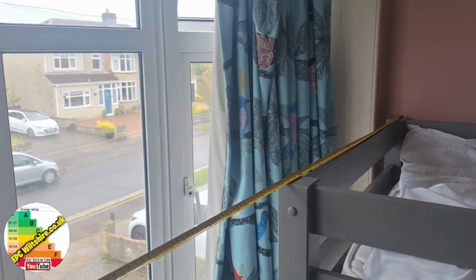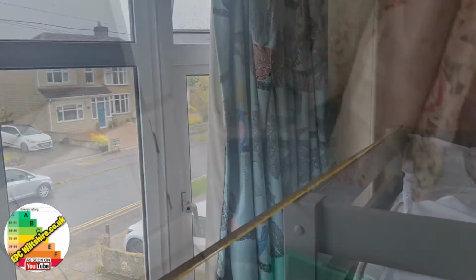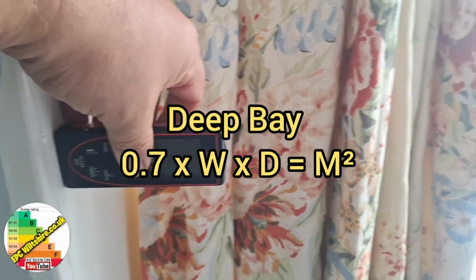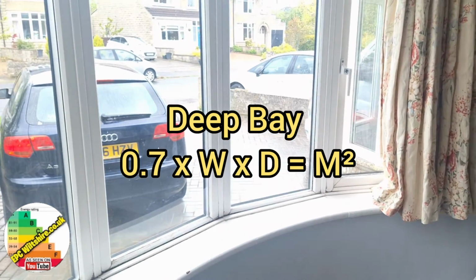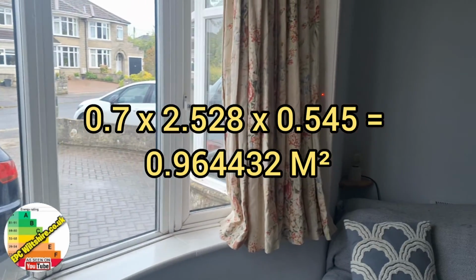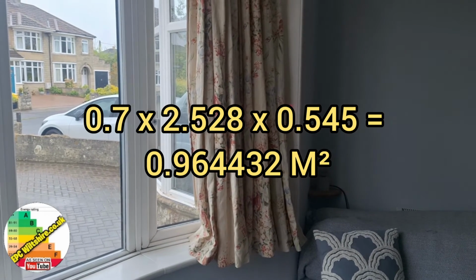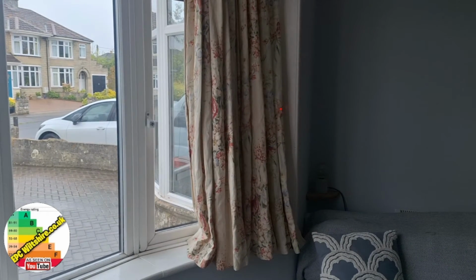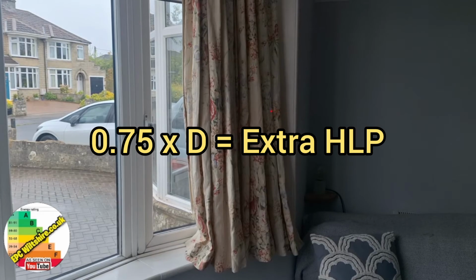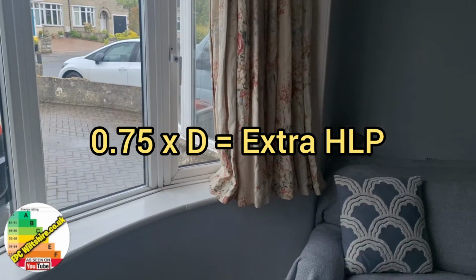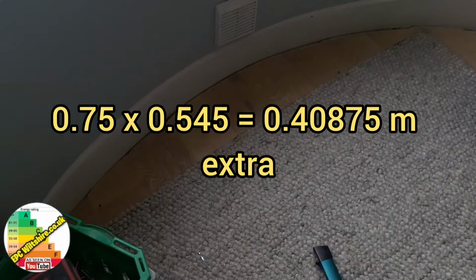So to calculate the meters squared and the extra heat loss perimeter of a deep bay, you take 0.7 times the width times the depth, and that equals the meters squared. The extra heat loss perimeter is 0.75 times the depth.